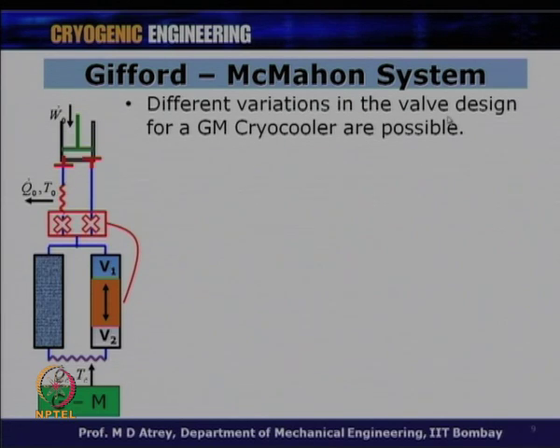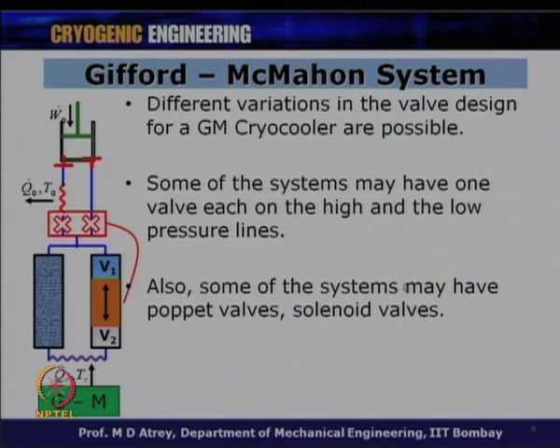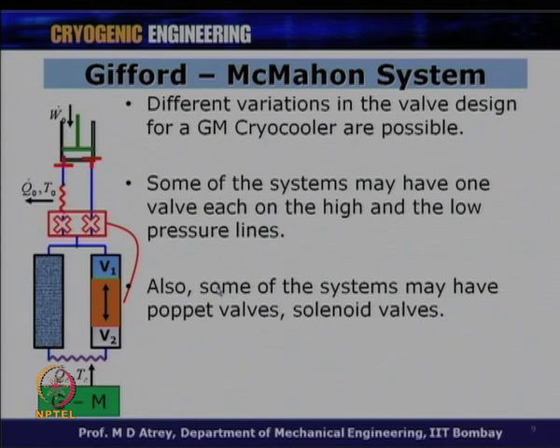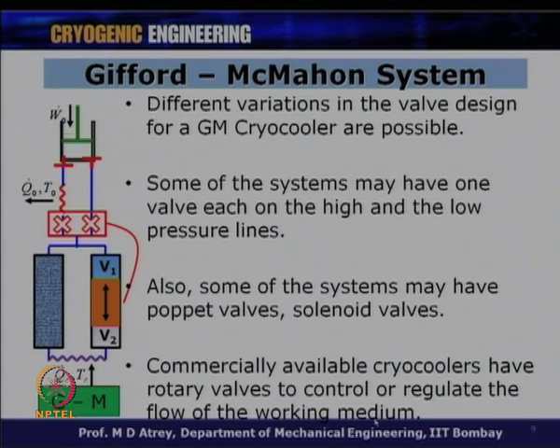The timing of the valves — opening and closing — is in relation with the position of the displacer, which is vital for optimum operation. In a GM system, there is a relation between the pressure pulse generated by the valve mechanism and the displacer motion. Different valve designs are possible: some systems have one valve each on the high and low pressure side; some may have poppet valves as in IC engines; some use solenoid valves. Most commercially available cryocoolers use a rotary valve driven by a motor.